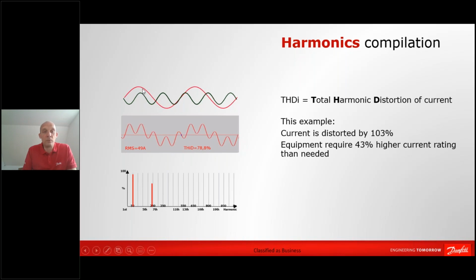And when you add those two frequencies together, then you will have a sum waveform looking like the one you have down here. What you also see now is that the RMS current went up. So we went from 39 to 49 amps, and the THDI value went up to 80%. That means now that if you look at this waveform here in the middle, you can say that it's 80% distorted from the ideal sinusoidal shape.